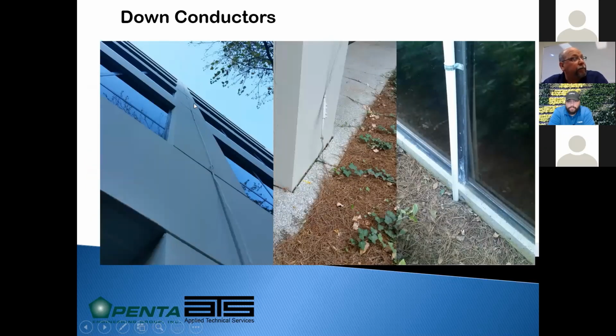Others allow it to just come down the exterior of the building, it still has to be securely fastened every 3 feet. If you use aluminum as the down conductor, it has to transition to copper within 18 inches of the ground. Aluminum conductor cannot be buried, cannot be in contact with the ground because it deteriorates rapidly with the soil conditions. And if the down conductor is in an area that's subject to physical damage, it has to be protected along the bottom 6 feet. So if the landscaping crew with their weed eater can come by and cut this, or if it's close to a walkway, anything else that may physically damage that conductor cable, we've got to protect it from physical damage.